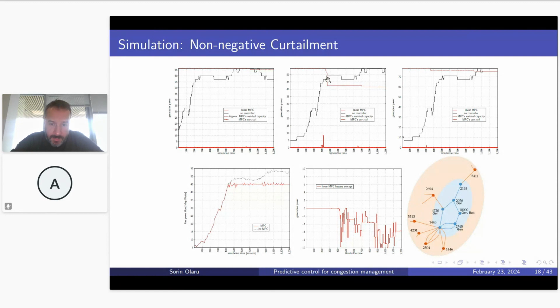And after this order of curtailment, as the trend is not followed with another increase on the lines, the control algorithm is discharging the battery. You see, it comes to zero and is ready for a new congestion event. And the congestion event appears, you see, it's the third unit that goes up, and this increase is able to be handled by the battery.